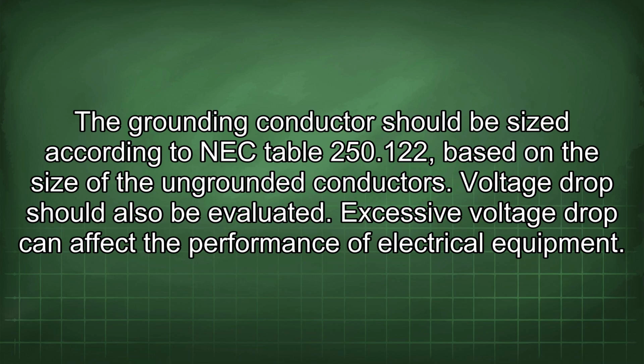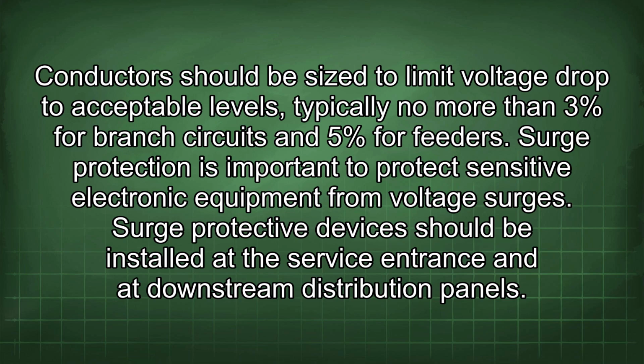Voltage drop should also be evaluated. Excessive voltage drop can affect the performance of electrical equipment. Conductors should be sized to limit voltage drop to acceptable levels, typically no more than 3% for branch circuits and 5% for feeders. Surge protection is important to protect sensitive electronic equipment from voltage surges. Surge protective devices should be installed at the service entrance and at downstream distribution panels.